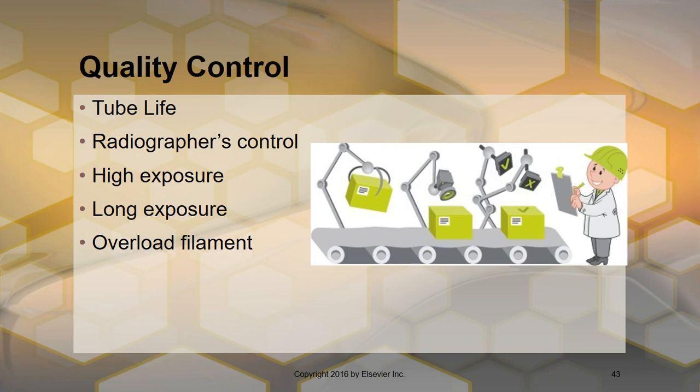What you also need to know is that if you heat it up by prepping the rotor, so if you're doing an X-ray, in today's world, it doesn't happen nearly as much as it did in my day, because we'd have to hold the patient, and then somebody would rotor up and say, okay, shoot, and then you have to hit the button. But just sitting there with it rotoring up, it's just like a car engine. If you just took your key and just let it go, but the engine's already going, and you hear that really hard sound, that's what would happen if you did that for too long. So you don't want to overload the filament.